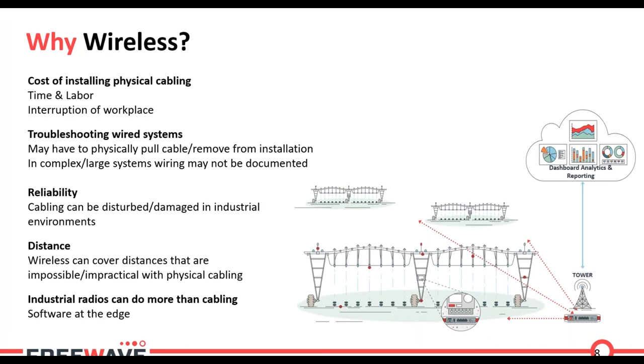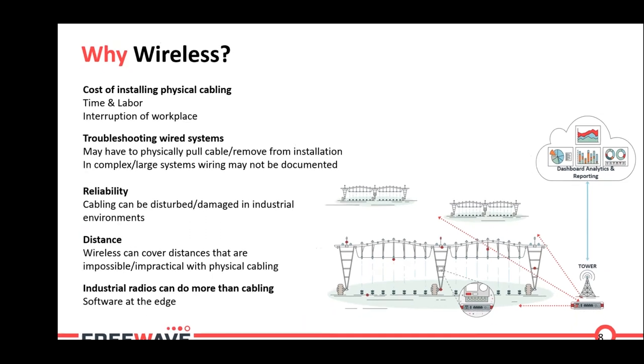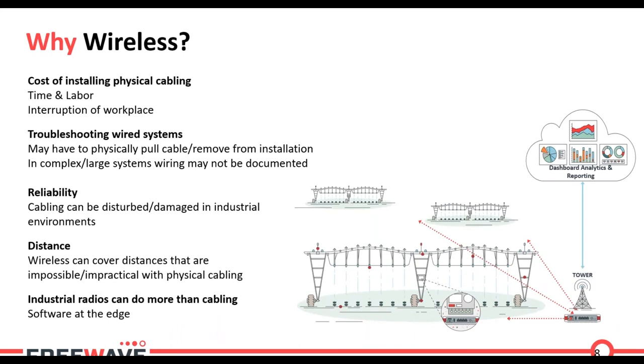Traditionally in SCADA, we have relied on something called poll response, where we send a question and we get a response to that question. So that's poll response. And the message has to traverse the entire network in order to make that decision. If you can make that decision at the edge of the network, we've reduced our latency and we've also eliminated the possibility of that link failing and not being able to make that decision. And we'll talk about that more in another slide here.